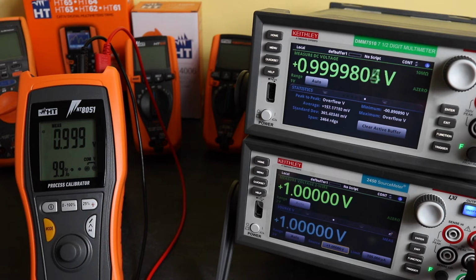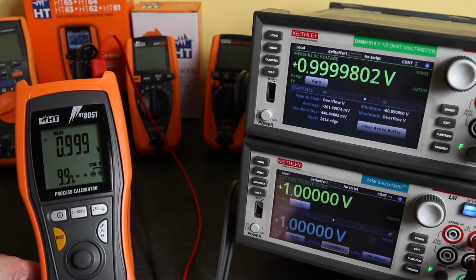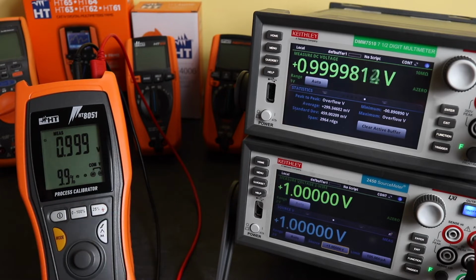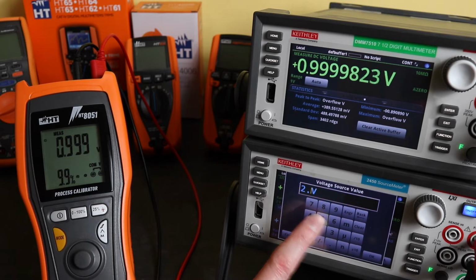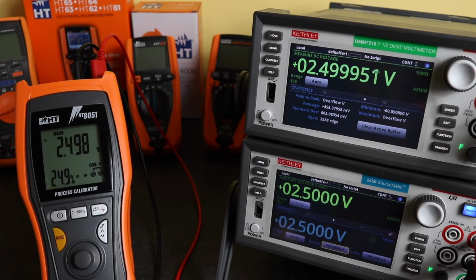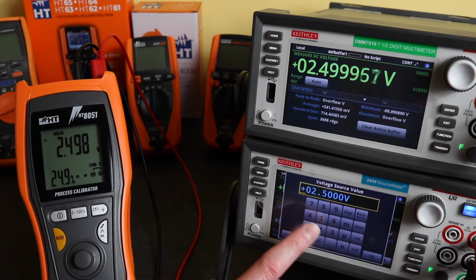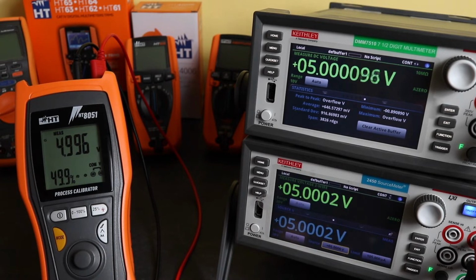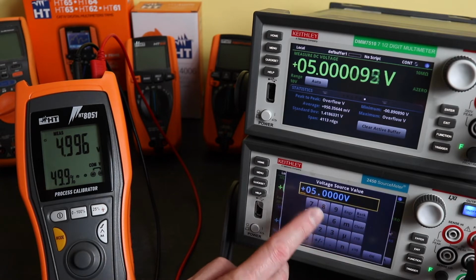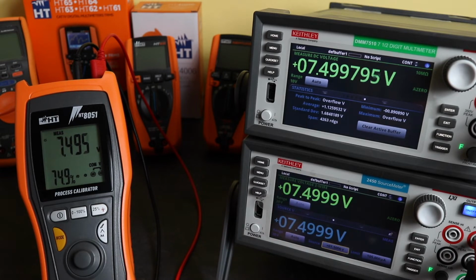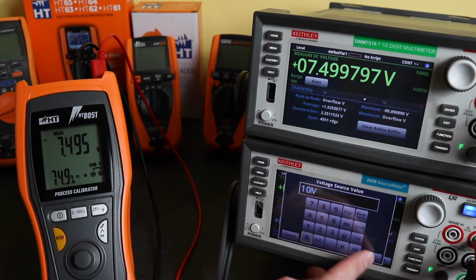Okay, so we're back with the instruments and we are measuring 0 to 10 volts on the HT8051 now, and we are supplying dead on 1 volt, but our DMM7510 is reading 0.99998, which actually correlates with the HT8051 there. So we'll take this up to 2.5 volts, 2.498, 2.499, 5, 4.996 against the 5.0001. Let's go 7.5, 7.499 against 7.495.